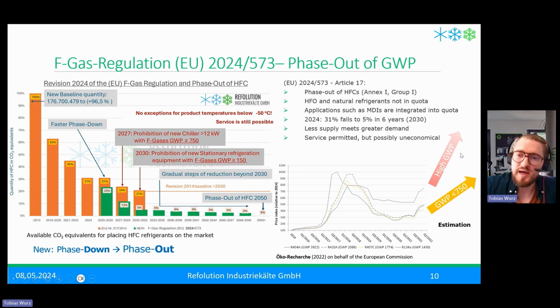We expect that the high GWP refrigerants will either explode in price enormously or you won't get any of this refrigerant anymore. Only for GWP below 750 do we expect that you can still get this refrigerant, but again with a high price increase, maybe 5 times or 10 times in that area. We have to see next year when the next step will come, and the MDIs are included too.